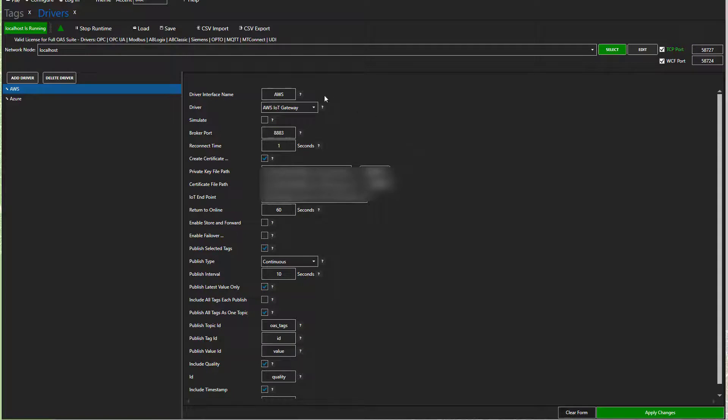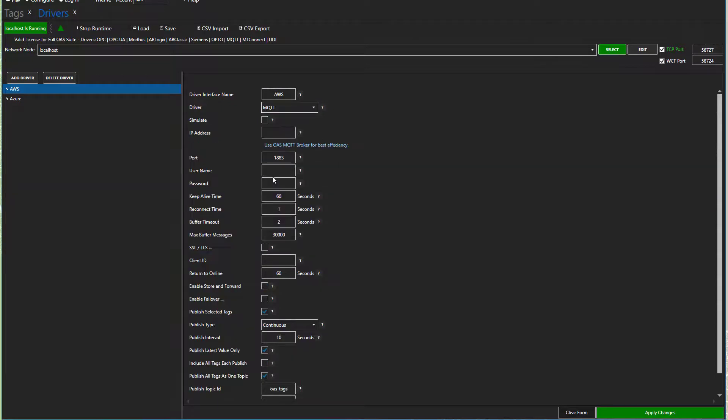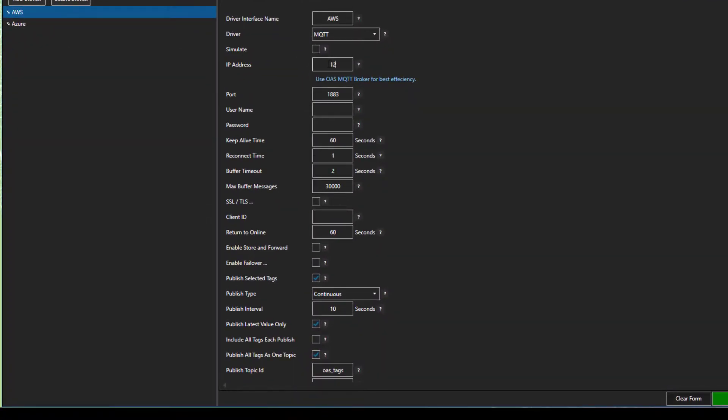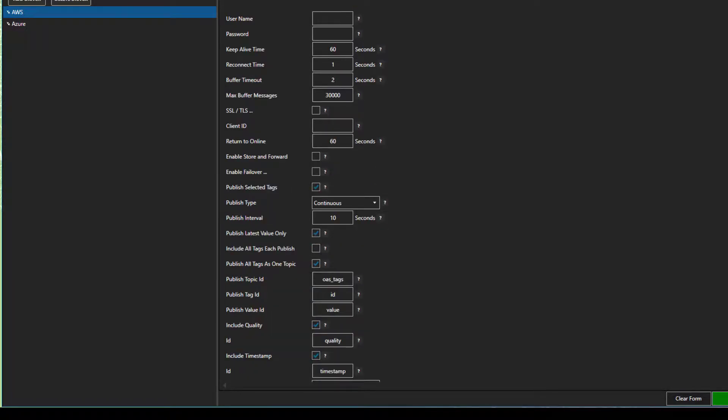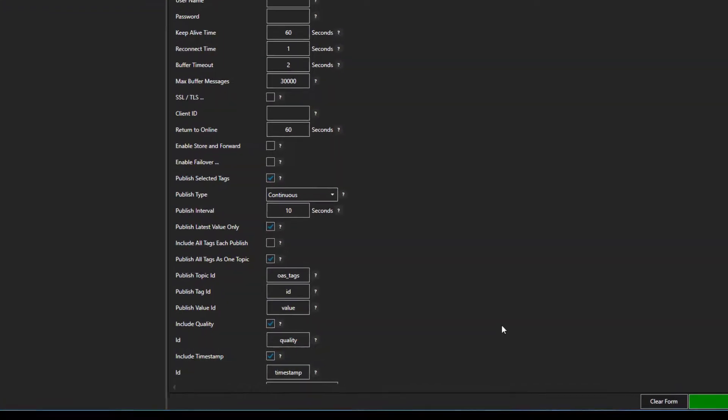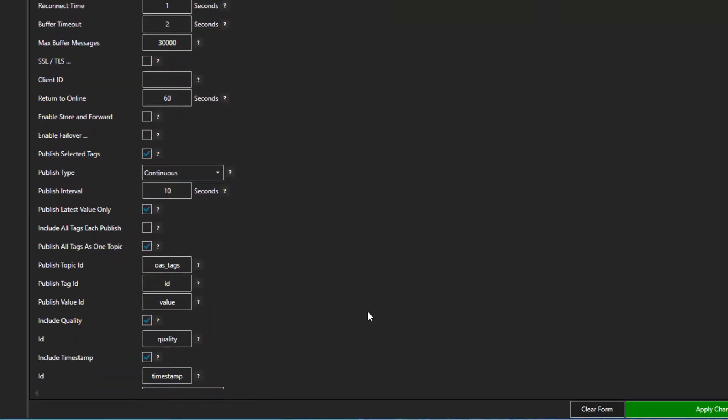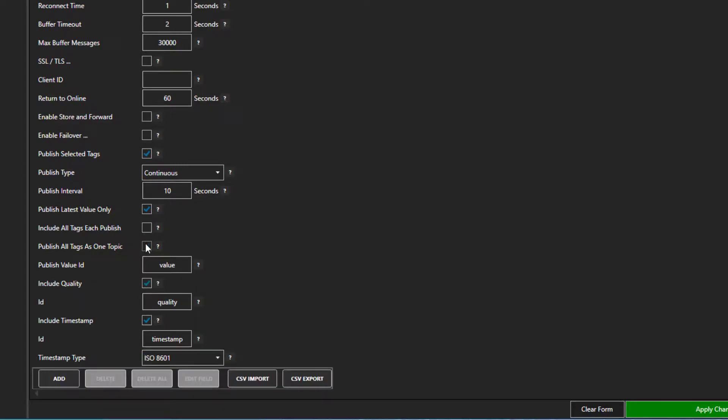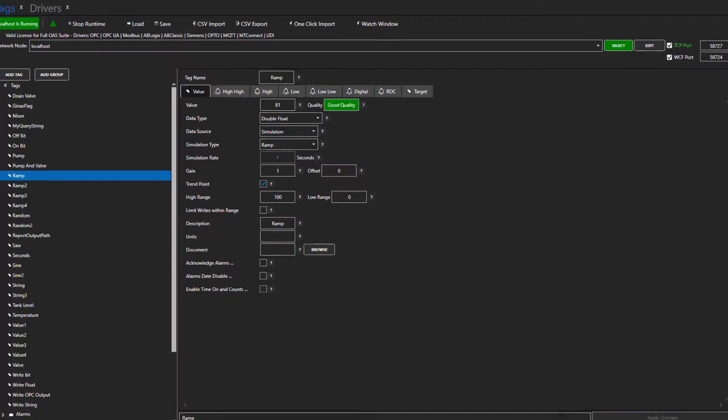Finally, let's look at doing our Bulk Publish to an MQTT broker. OAS can be both an MQTT broker and an MQTT client. For the Bulk Publish, we will use OAS as an MQTT broker. I am going to put in my local IP address here because I have the OAS broker on my own machine. You would enter the credentials for whatever MQTT broker you are publishing to. Down here, in the Bulk Publish settings, I am going to uncheck Publish All Tags as One Topic. I will make the publish interval just 0 seconds. By doing this, it will publish every time the tag value updates. So let's go over to our ramp tag and set its simulation rate to 0.1 seconds. I will add this new driver to the service and then we can go over and set up our MQTT client.